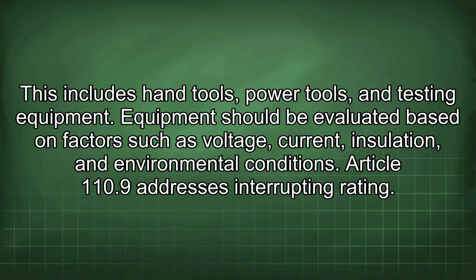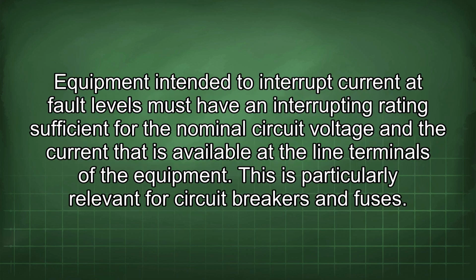Article 110.9 addresses interrupting rating. Equipment intended to interrupt current at fault levels must have an interrupting rating sufficient for the nominal circuit voltage and the current that is available at the line terminals of the equipment. This is particularly relevant for circuit breakers and fuses.